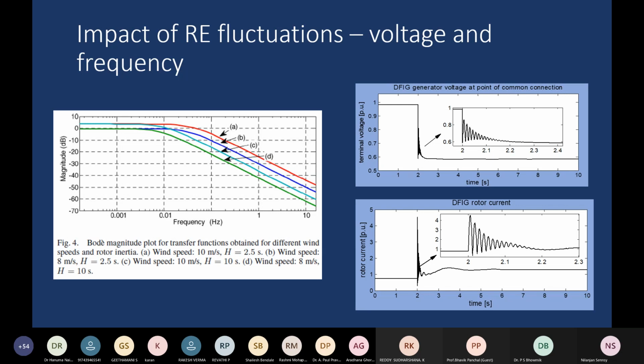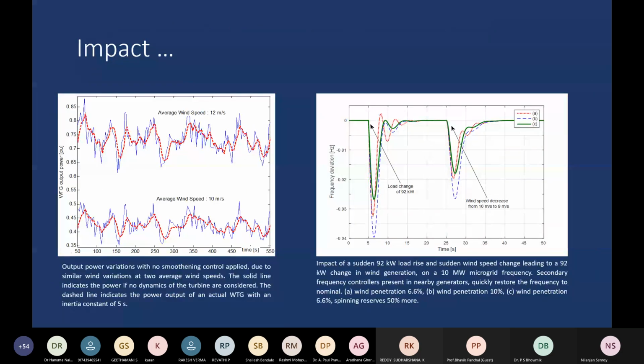So some countries, like for instance the UK and Germany, mandate that a DFIG must inject reactive power into the network when there is a voltage sag. In India and Ireland, the Irish grid code and the Indian grid code, they mandate that some wind turbines should actually continue to inject active power even when the voltage quality is poor. So these different kinds of grid codes expect different kinds of behavior from the wind turbines.